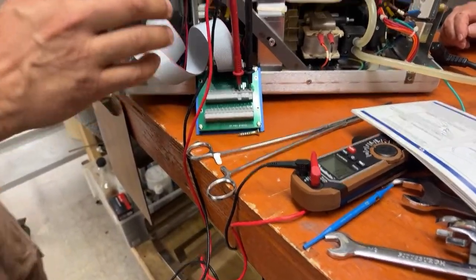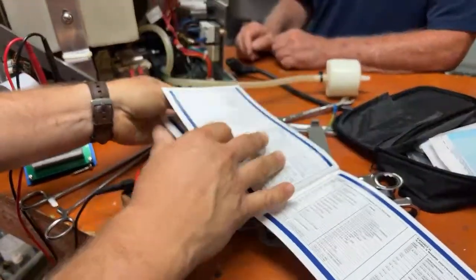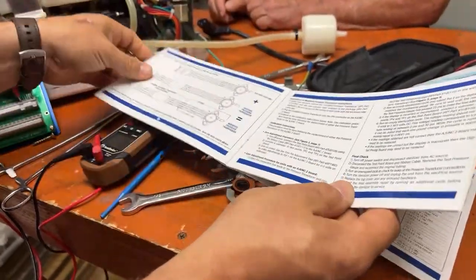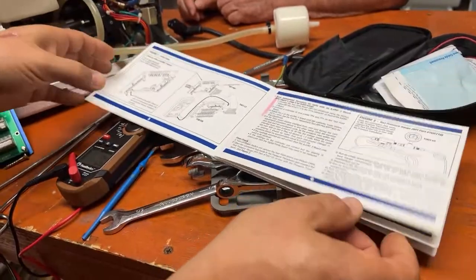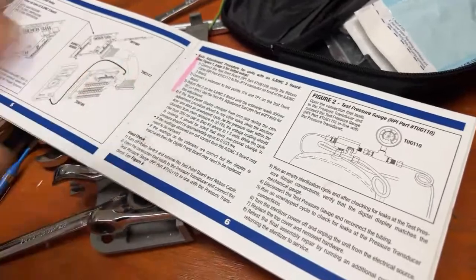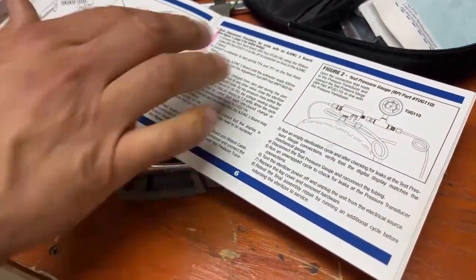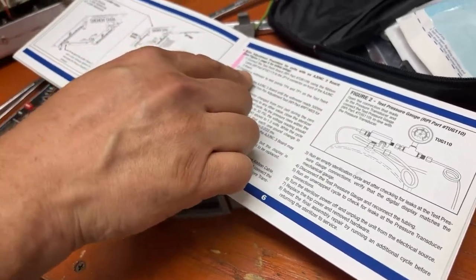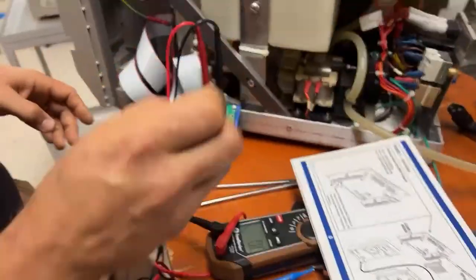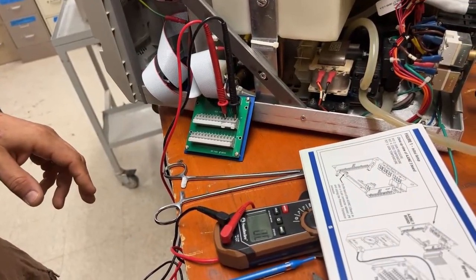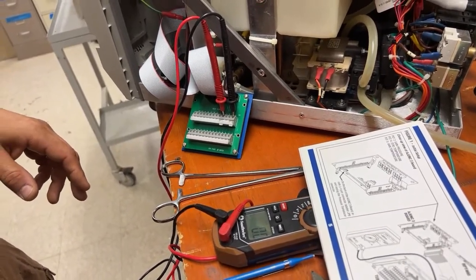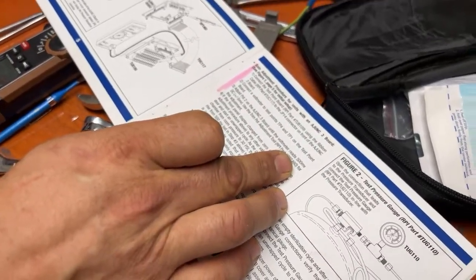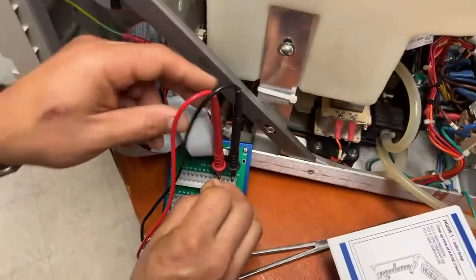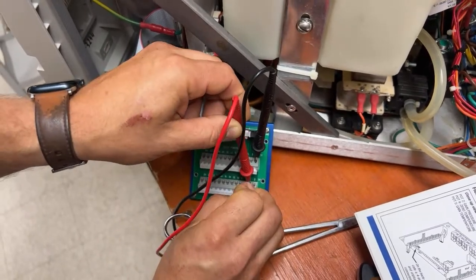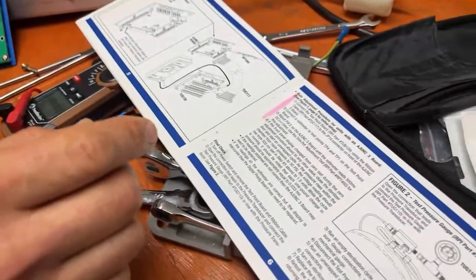So what we're going to do is find the procedure where, okay, this is where we're going to do the final test, or final adjustment, of potentiometer 2. So now connect the test point board using the ribbon cable, we already did that. Now connect the voltmeter to test point 4 and 1. On these, it doesn't say polarity. I don't think it cares because we're just doing 500 millivolts. All right, so test point 4 and 1. I'm going to take it off of 7 and put it down here onto 4. All right, and then our reading is 500 millivolts. So we're on volts DC.